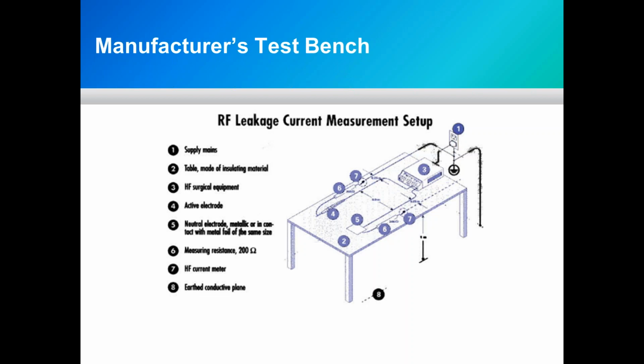Now, as biomeds, we don't have to have this table. We don't have to have such an exacting layout. But what we should try to do is ensure that our leads are as short as possible, that the leads are not coiled, that we're not adding capacitance by them looped across a chassis, or opportunity for cross coupling between one lead to another, or coiling it to get some additional inductance in the test lead.